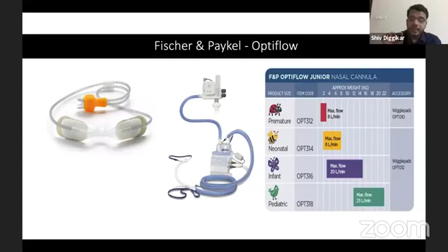With Fisher and Paykel, the flow rate can be anywhere from 1 to 60 liters. However, in neonates, more than 8 liters is not recommended at all. Humidity is about 100%, and gas temperature is about 34 to 37 degrees Celsius. Sorry for the error.